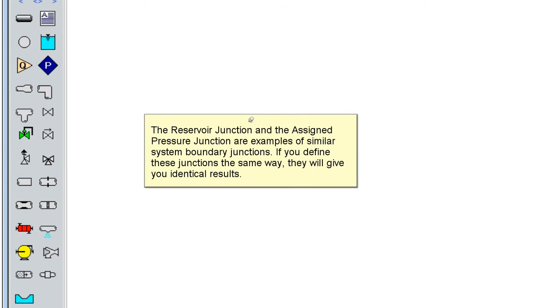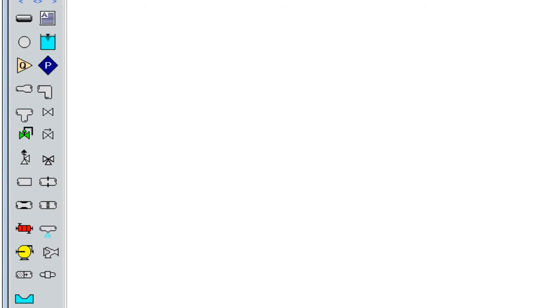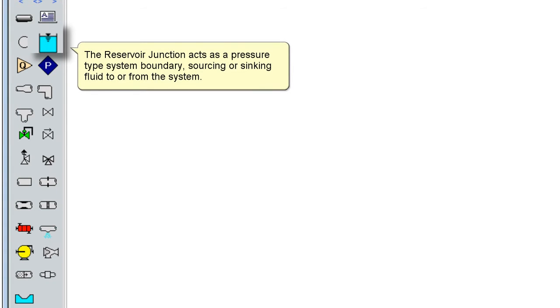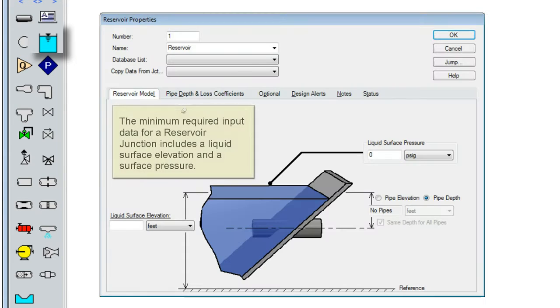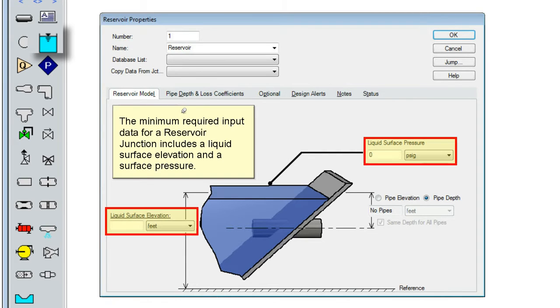The reservoir junction and the assigned pressure junction are examples of similar system boundary junctions. If you define these junctions the same way, they will give you identical results. The reservoir junction acts as a pressure type system boundary, sourcing or sinking fluid to or from the system. The minimum required input data for a reservoir junction includes a liquid surface elevation and a surface pressure.